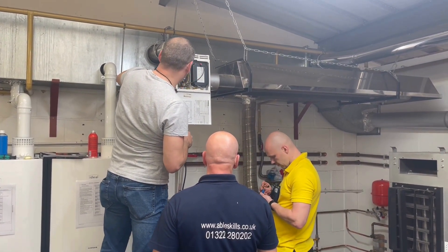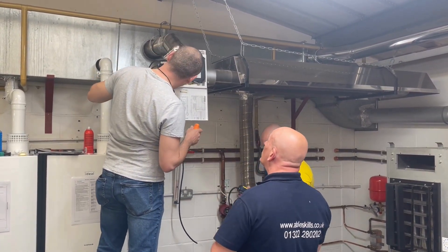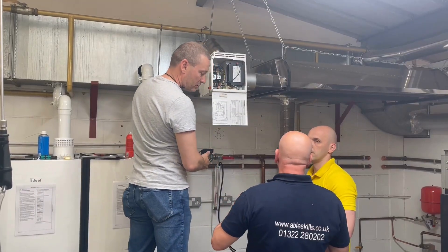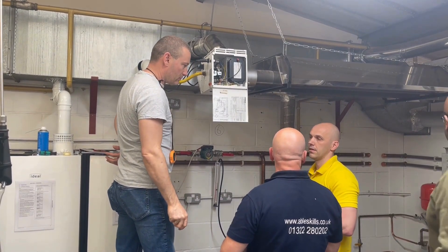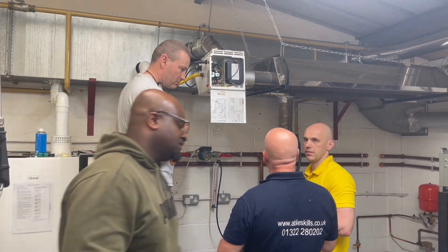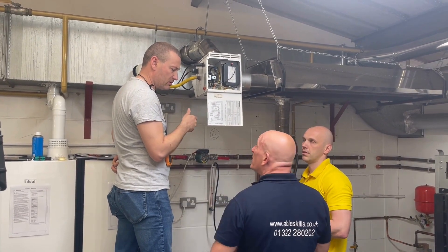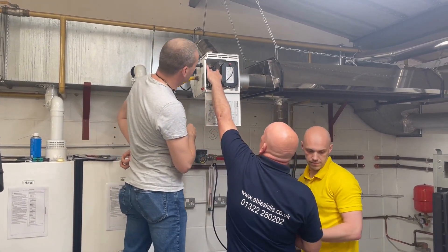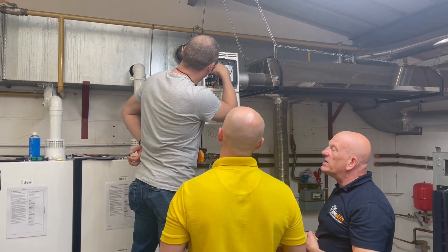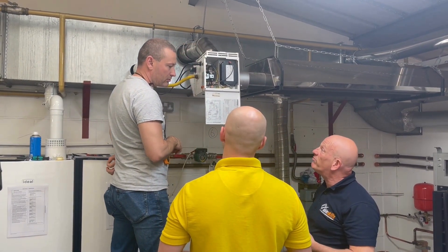So we have a pressure switch. Check the burn pressure. What device controls the burn pressure? Pressure function. What devices control the pressure? So you have a regulator — an appliance regulator. That's why you are doing the burn pressure. So what you will do is check the burn pressure and verify if the regulator is maintaining it.